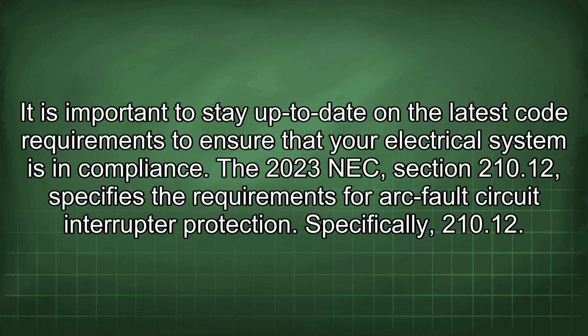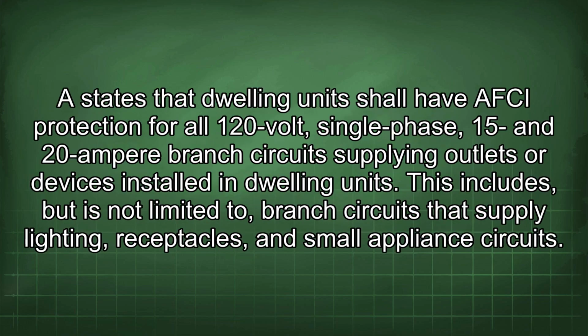The 2023 NEC Section 210.12 specifies the requirements for arc fault circuit interrupter protection. Specifically, 210.12 states that dwelling units shall have AFCI protection for all 120-volt, single-phase, 15 and 20 ampere branch circuits supplying outlets or devices installed in dwelling units. This includes, but is not limited to, branch circuits that supply lighting, receptacles, and small appliance circuits.